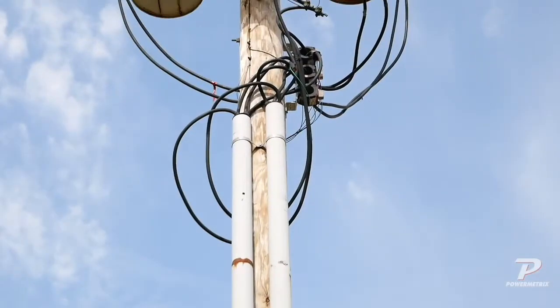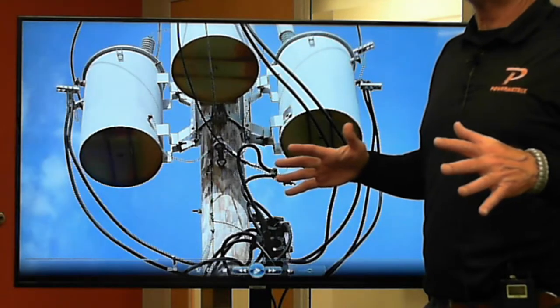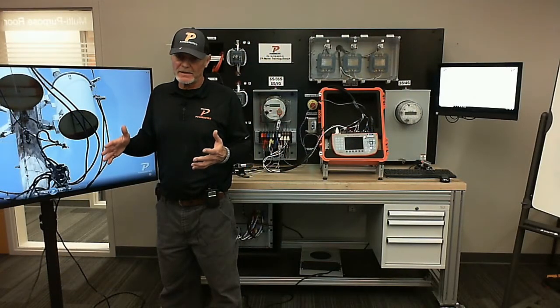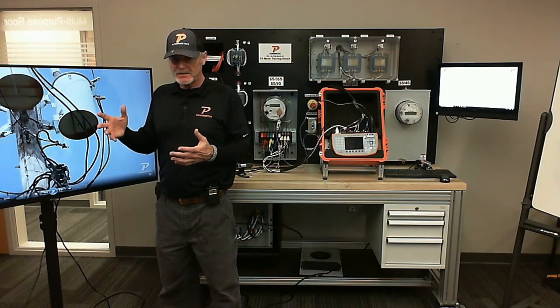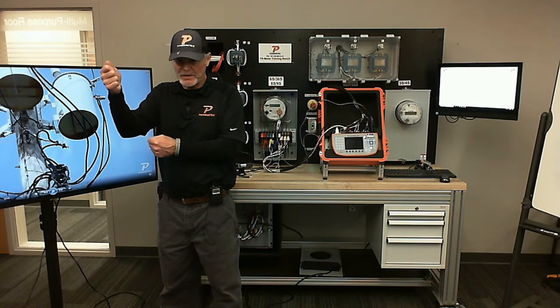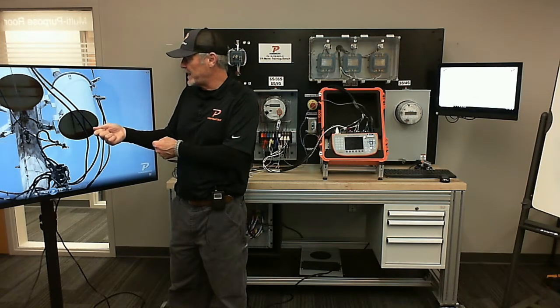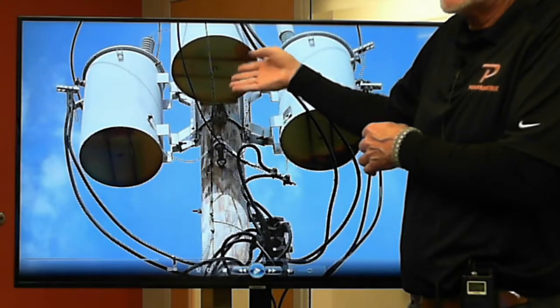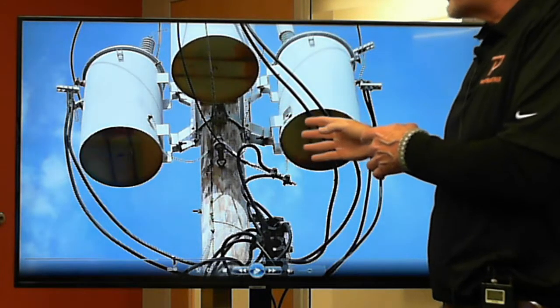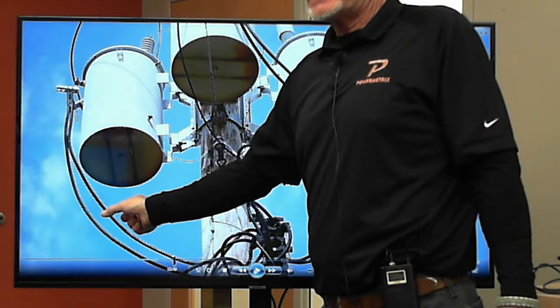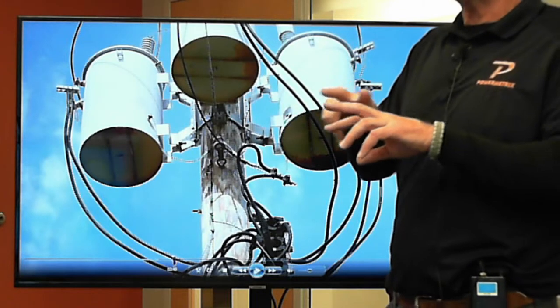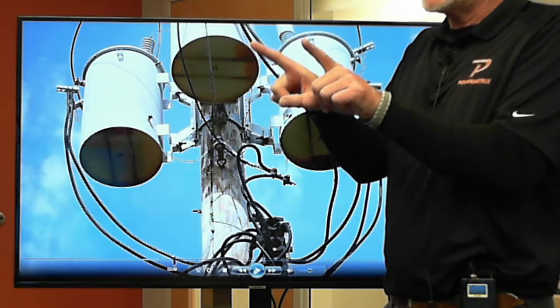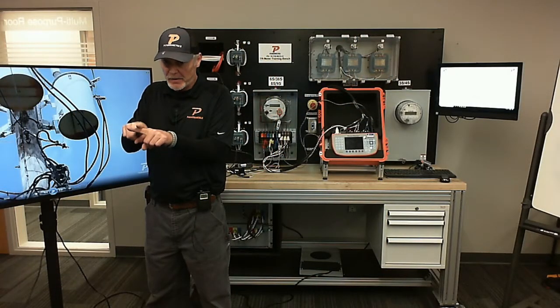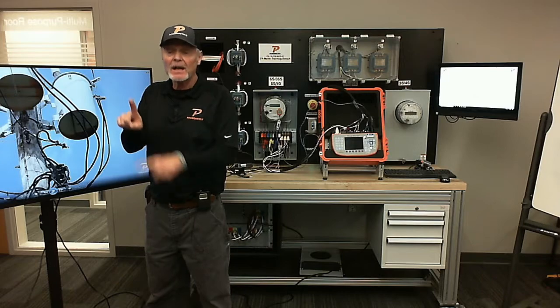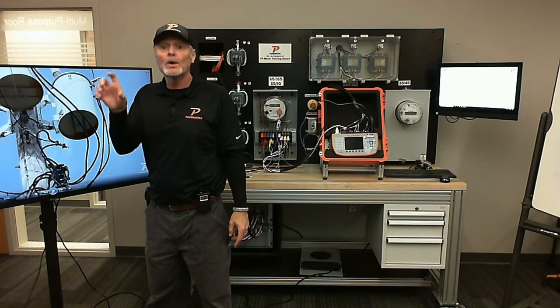To follow up on what I was saying, I've had this question asked a lot. When you get up there, everything might not be labeled well, so you don't know which is A, B, or C phase. When you start testing the CTs with a high volt probe on your extendo stick, you get up on the first phase - chances are that's going to be B phase, since the center phase is usually B. But you might actually be on C instead of A. Remember, we get that cross phase connection, and it will show those phasors crossed - the wrong colors together on my phasors or vectors. The equipment itself will also tell you cross phase connection.